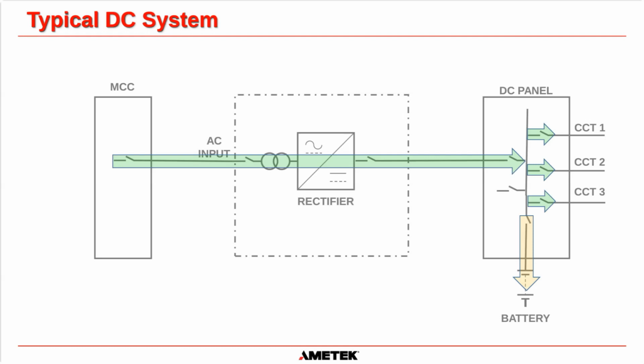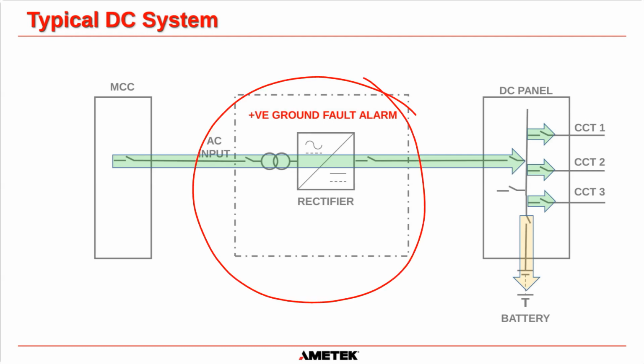So we're going to go back to the typical DC system and how we find out actually where the ground fault is. If your charger has a ground fault alarm on it, you want to know where it is, obviously, so you can clear it and go back to normal operation. So here we have our normal typical DC system that we started off with earlier on in the slide. And we've got a positive ground fault alarm on our charger rectifier here. Okay, it's saying we have a positive ground fault alarm.